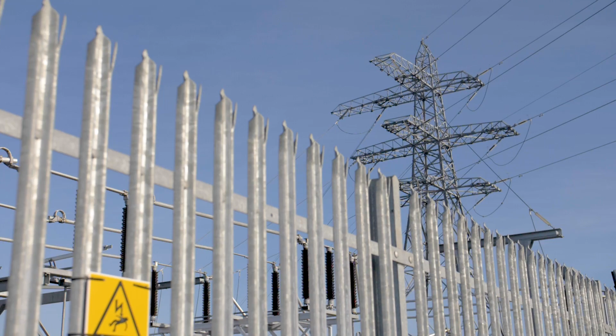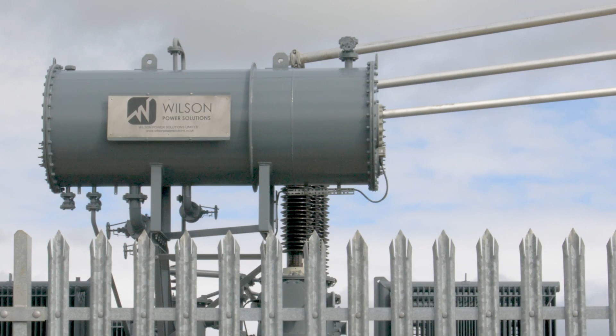All the communication and control systems on the windmills transmit data via fibre optics to this point, then on to our service team so they understand how the windmills are performing. Inside the substation, behind me, is the big transformer. We generate at 11,000 volts from the windmills, through the cables, up through the meter, into the transformer, which steps it up to 132,000 volts in this case, then transmits over into Western Power Distribution's side and on to the network.